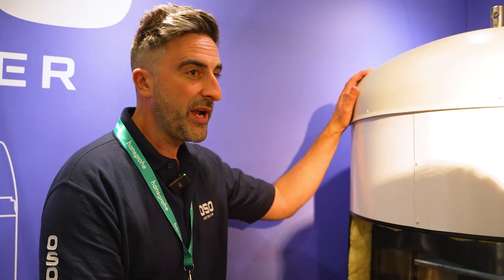Is this still an indirect cylinder? Yes, this is an indirect cylinder — we're not talking thermal store here. No, indirect cylinder. This is a 135 kilowatt coil on the 600 litre unit. On the 1000 litre it's a 200 kilowatt coil. So we can transfer that energy much quicker.